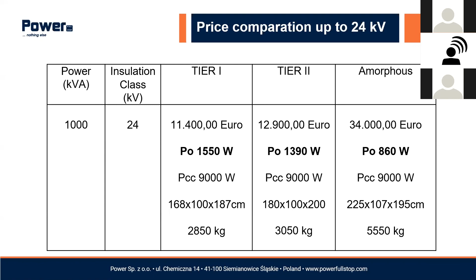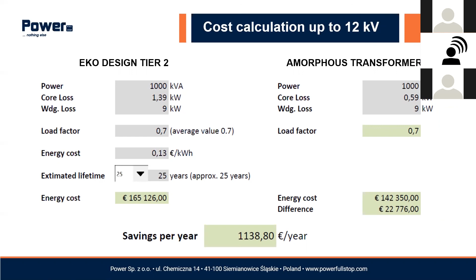By the way, the costs here are just indicative. I just took the market costs. These are not our prices, just for your information. So I made also some comparison. How much can you save using tier 2 and amorphous transformer? As you can see, the yearly difference is around 1,150 euro. In 25 years, you are saving around 22,000 euro. So it's quite important. Here you can see the graphics. The red line is for tier 2, the blue line is for amorphous. I'm just comparing 2000 kVA transformers.